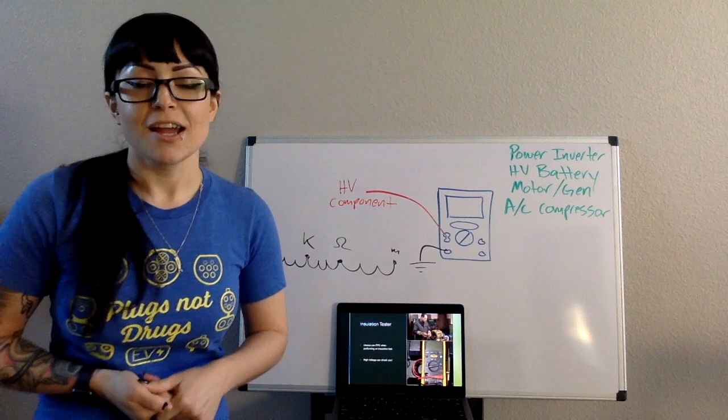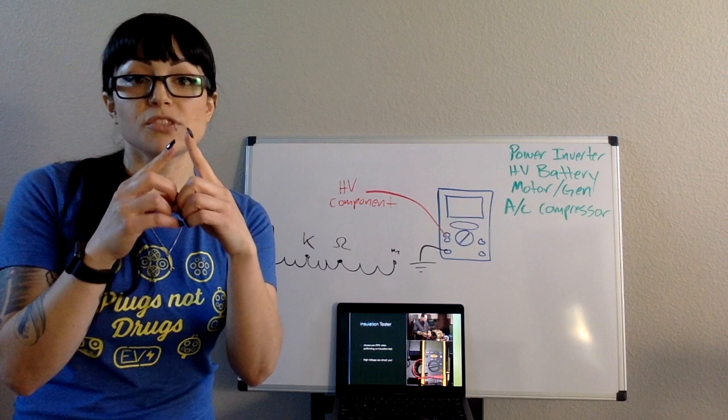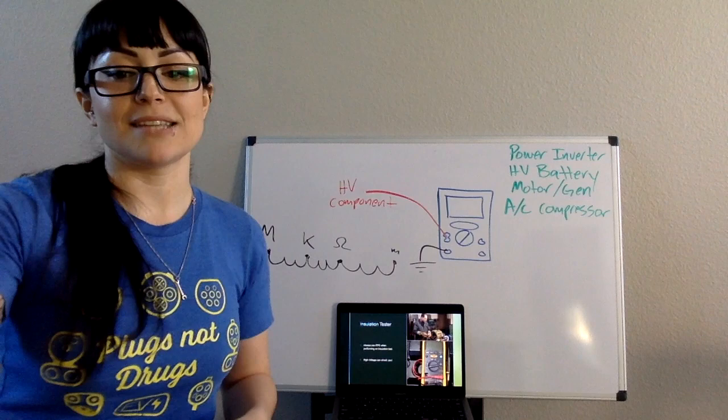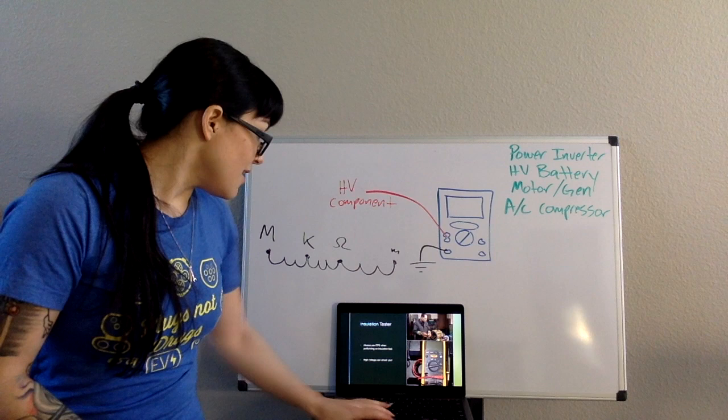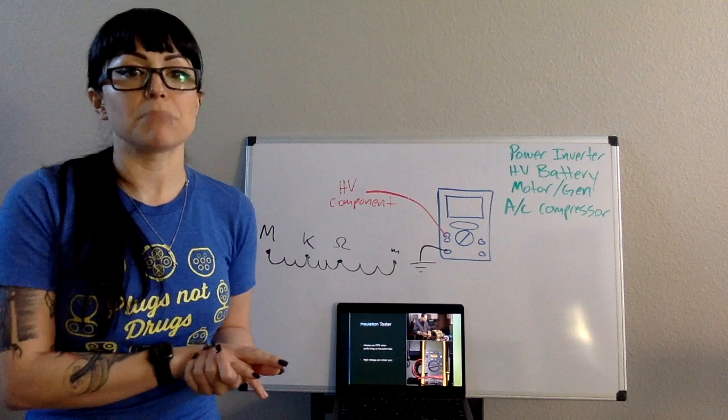The issue is that it's probably not going to feel good to get tased by your meter, so you're going to want to use high-voltage gloves on this one. Normally in class when I talk about this, I'd show you guys the leads. I'd turn off the lights, put the leads close to each other, and hit the insulation test, and you can actually see the spark jump because it's got so much voltage. You don't want to get shocked by that. In the picture on the side, you can see the gentleman is using high-voltage gloves because that meter can shock you as well.